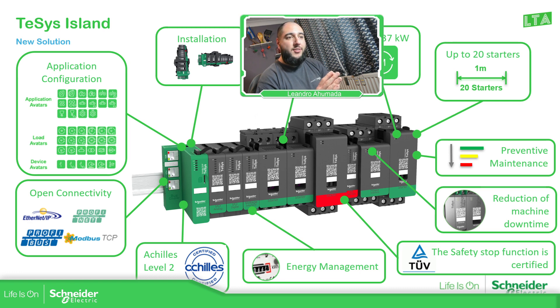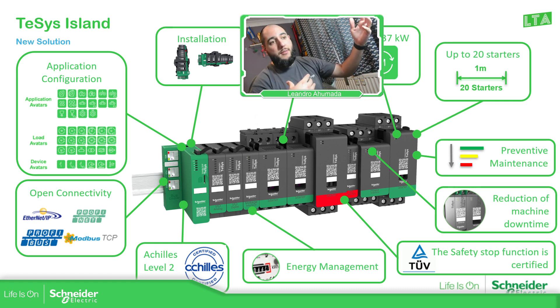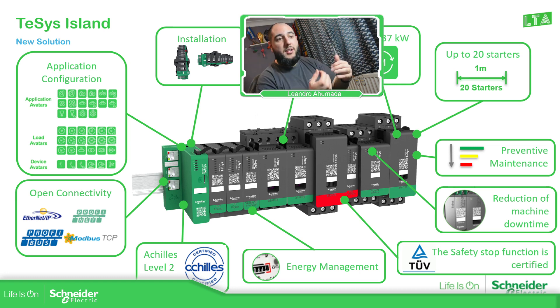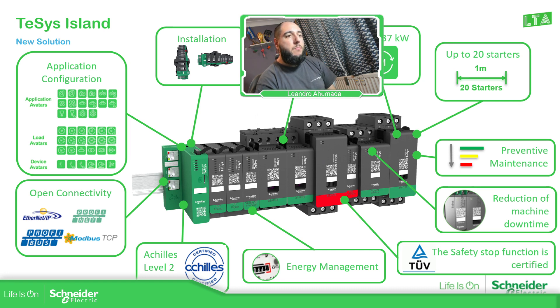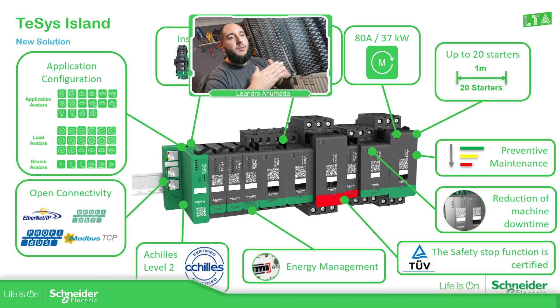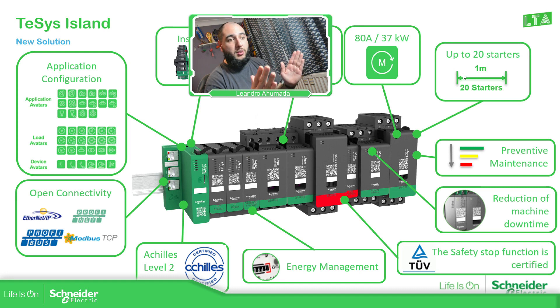This is more than just having the contactor with the overload. We have the possibility to use energy management. If you already have the contactor with all the protection and activation of the motor, plus a power meter, you can replace that and have everything in just one island. We can have energy monitoring for each device using only one voltage interface. Installation can be vertical or horizontal. Regarding limitations, we cannot expand this to infinity — we have a limit of up to 20 starters or up to one meter in length.